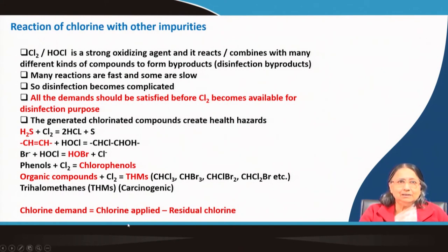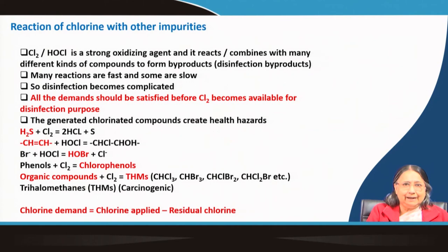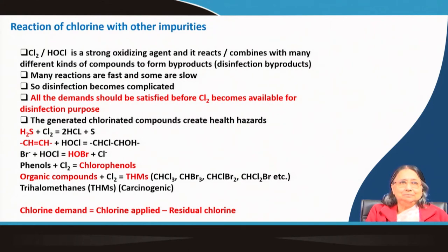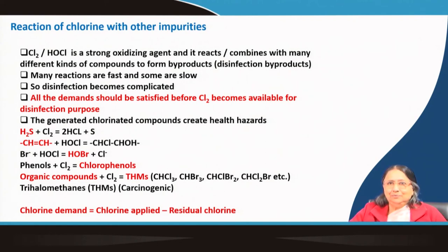Chlorine demand is defined as the chlorine applied minus the residual chlorine remaining after a contact period. The demand must be met first; only after that will free chlorine be available for disinfection — before that, it is consumed by other reactions.